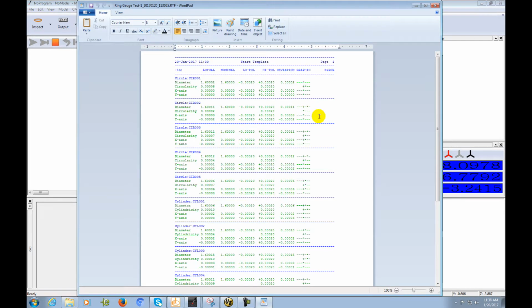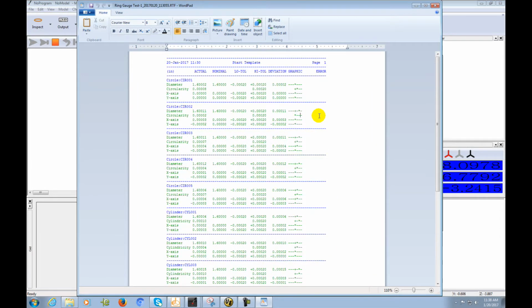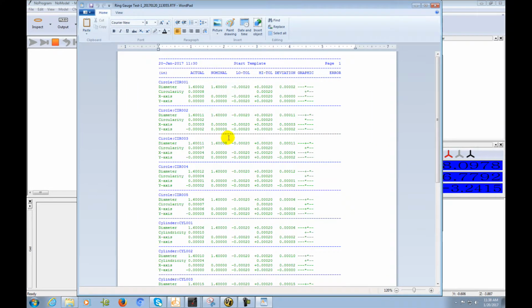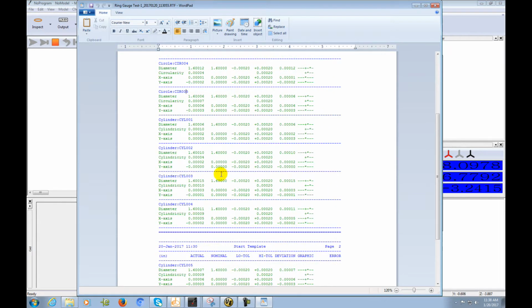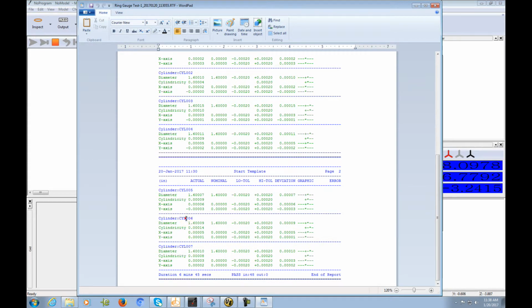Here is the RTF report, and let me make it bigger so you can see the details clearly. One thing you need to know, if you're not very familiar with PH20, is that you don't have to calibrate all those individual angles. You only have to calibrate a few different positions as an inferred calibration, and then you can use those angles anytime, anywhere you want. All these results show very high accuracy, and even with a cylinder that we measured at a very low position, you still get very high accuracy. You can see how fast, accurate, and flexible the PH20 is in measuring features.